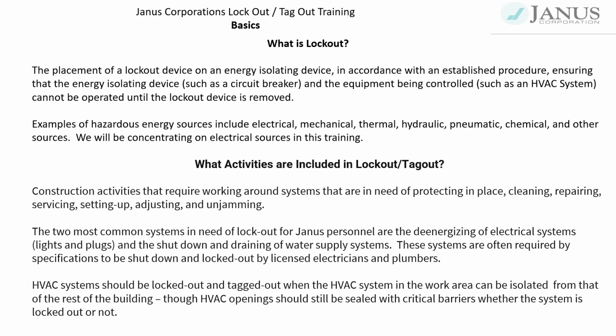Examples of hazardous energy sources include electrical, mechanical, thermal, hydraulic, pneumatic, chemical, and other sources. We will be concentrating on electrical sources in this training, as that is the most common type of lockout tagout issue Janus workers face on projects. Lockout tagout activities include construction activities that require working around systems that are in need of protecting in place, cleaning, repairing, servicing, setting up, adjusting, and unjamming.